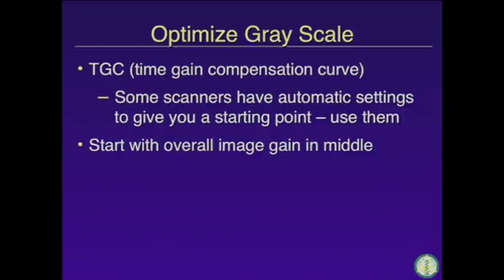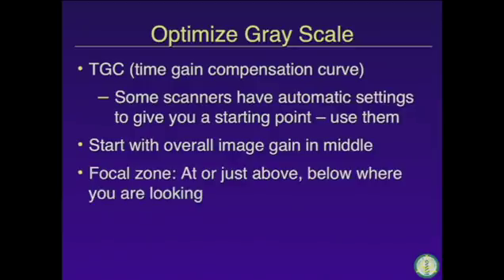So when you're going to use the TGC curve and you're just coming on that scanner, somebody else has used it before you, start with the overall image gain in the middle and put that TGC, the trim pots, in the middle as well. And once you've balanced it, then you can start moving the image gain up or down. Then you need to put the focal zone at or just above or below where you are looking. So on some scanners, it seems like you get a little bit better focus on the area of interest if you put the focal zone above it, on some below it. Now some manufacturers are saying we don't need to even focus it, we're focused throughout the field. You just need to learn where your manufacturer says is optimum for a focal zone if it's available.